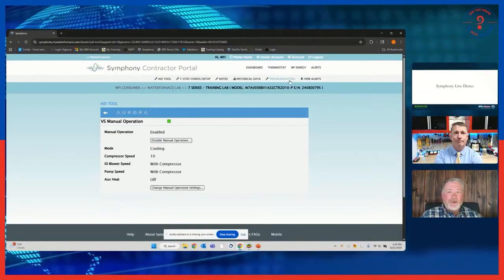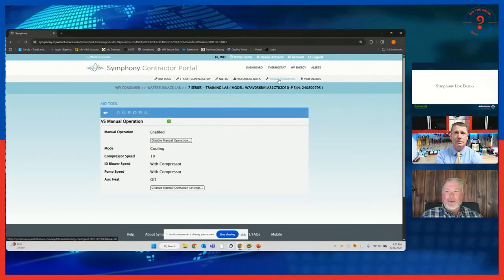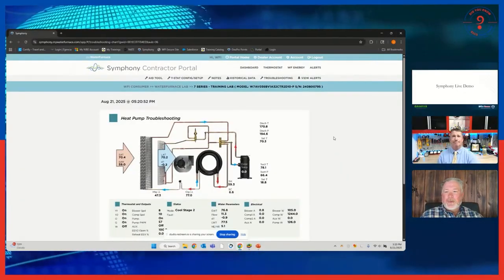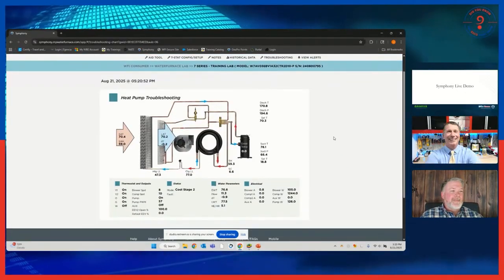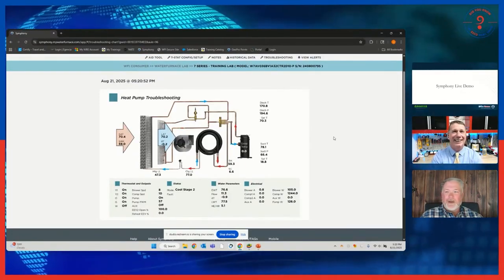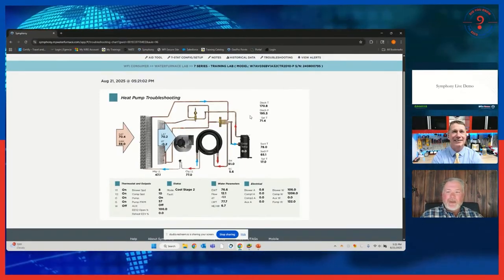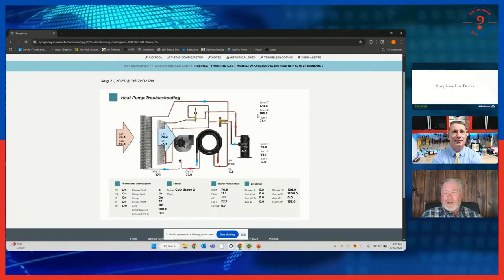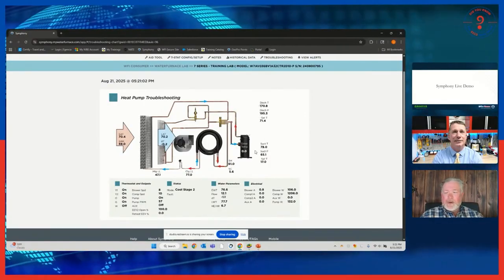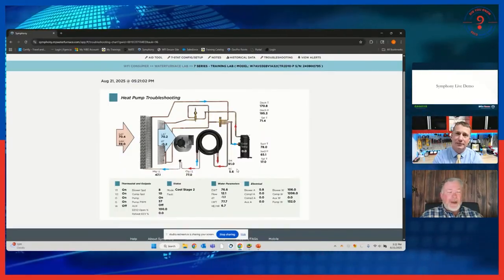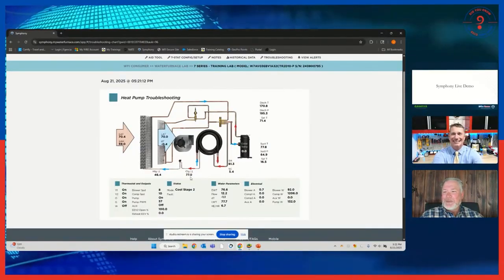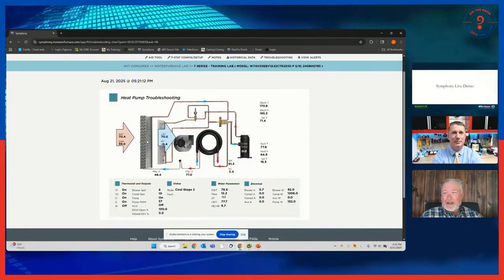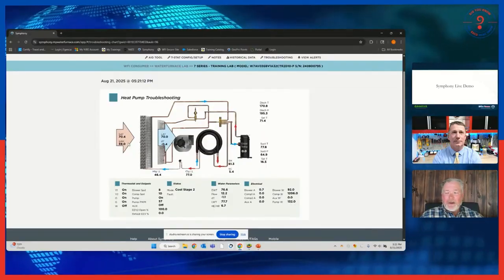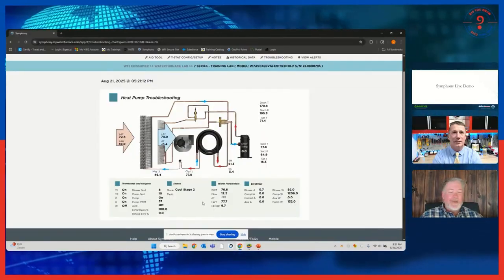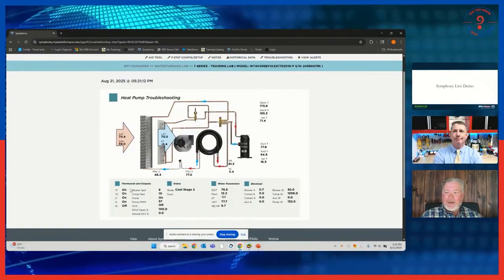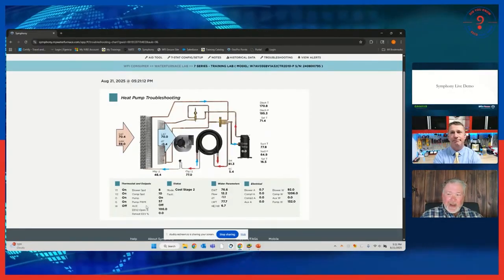The cool thing is, like I showed you with the troubleshooting chart earlier, I can come up here to troubleshooting and see all the inputs. It's already filled out and ready to go. I've got discharge temperature, which figures my saturation temperature, discharge pressure, suction pressure and temperature, superheat and subcooling, which look strange on an inverter if you're not used to it, cooling liquid line, heating liquid line, air delta T, entering air humidity, true enthalpy — everything is there.